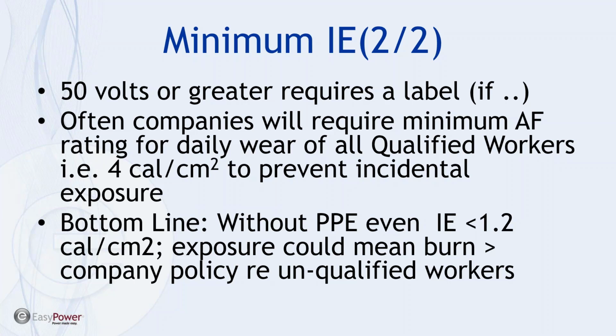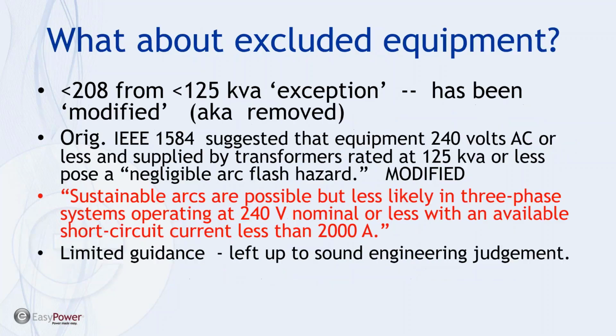But the bottom line, and this is something I'd like to reiterate, is that even without PPE below 1.2 calories per square centimeter, if our bare skin were exposed to that level of energy, it could mean we could be burned. So even though there's no requirement by NFPA for additional PPE, I think we need to have a discussion as far as company policy requiring it of unqualified persons, or anybody in the area, even though it's indicating less than 1.2 calories per square centimeter.